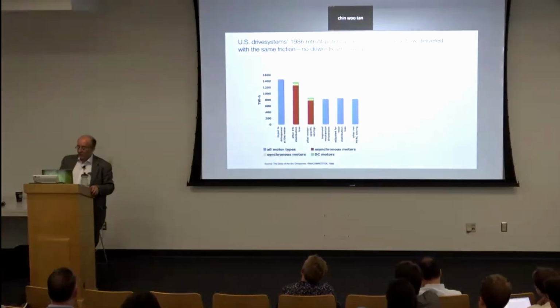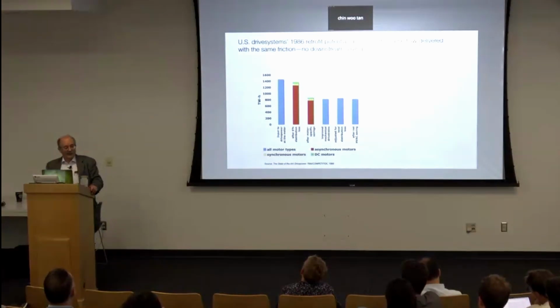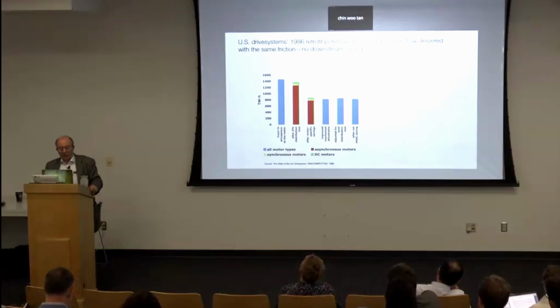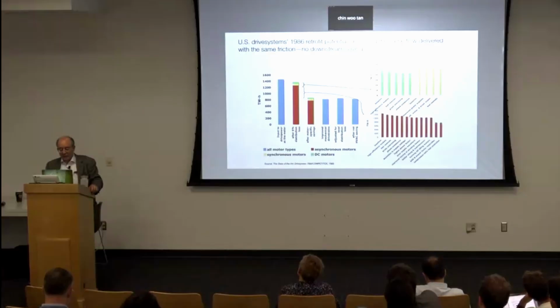While you're making the pumps, fans, and motors about 5 to 10 times smaller, because you fix the pipes and ducts first, you can also do 34 other things to the motor systems that collectively save about 3 to 5 times more energy than just the usual 2 improvements of high efficiency motors and adjustable speed drives.